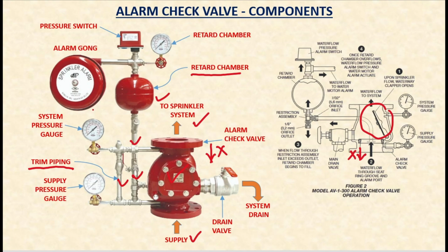Okay, and the next we have this part, drain. See this part, drain actually. This is called the drain valve. So the drain valve basically has two functions. One, to drain the system. Suppose for maintenance purposes you want to take all water out, you can open this valve, then all water will be drained. And next is for testing purposes. Suppose you want to test the system without actually operating the sprinkler, without actually a fire, you can open just this valve. So it will give you a real life test. So this valve basically can test the system or drain the water.